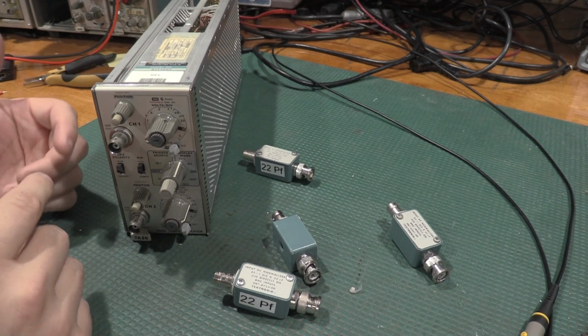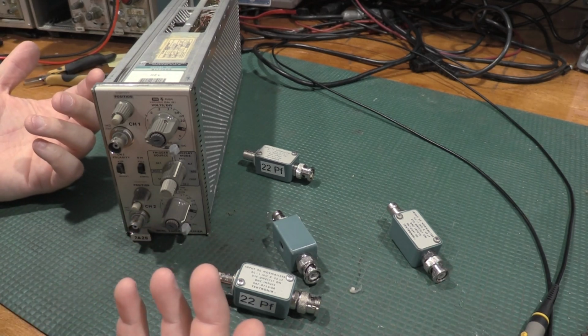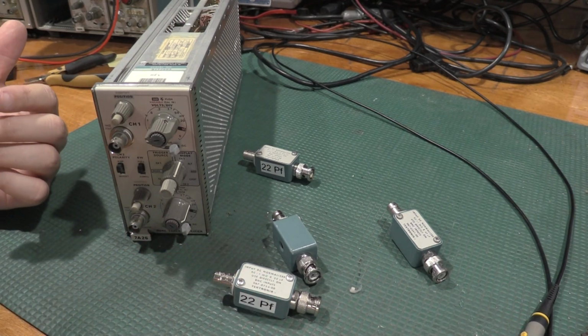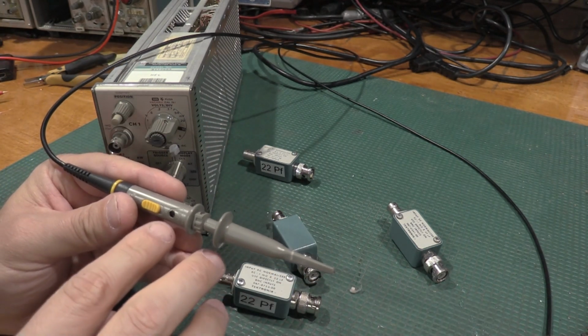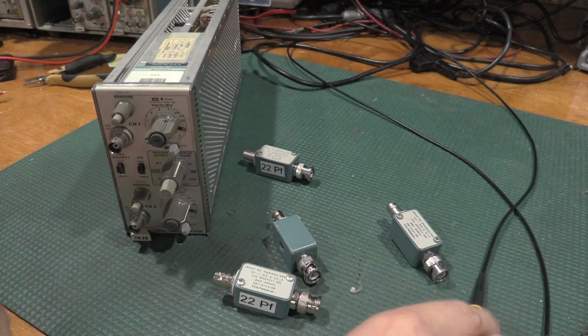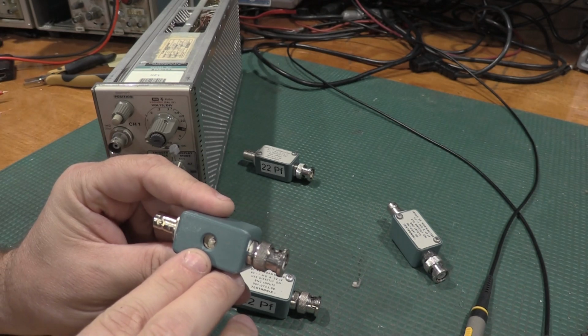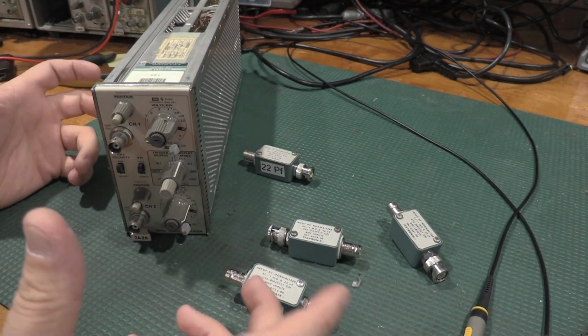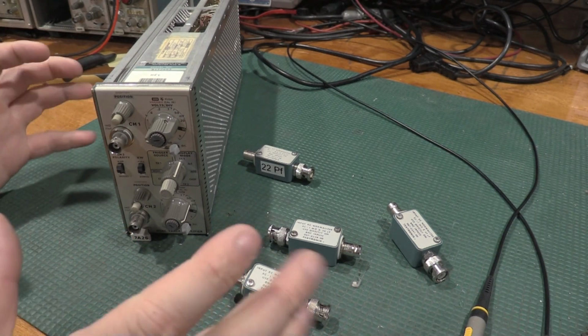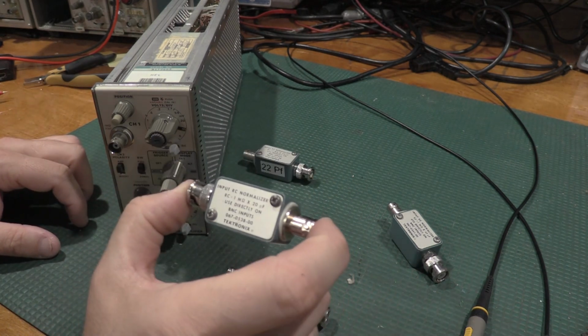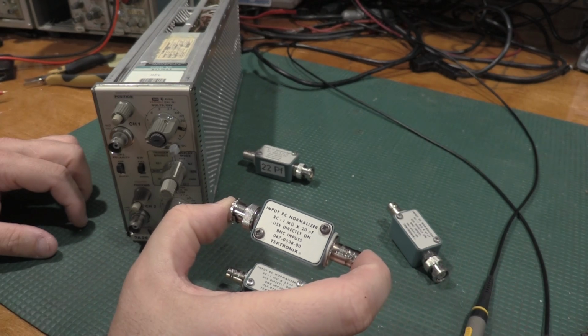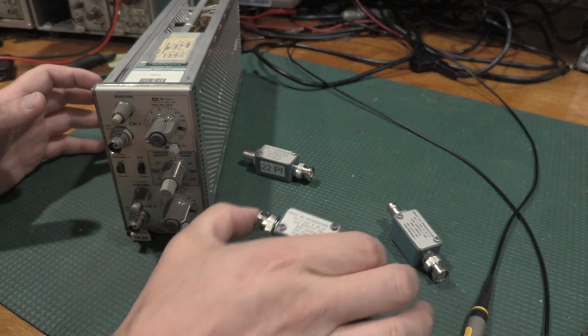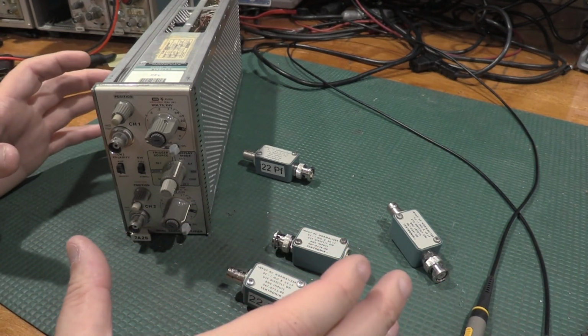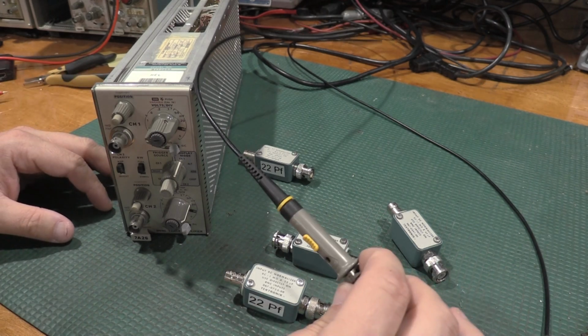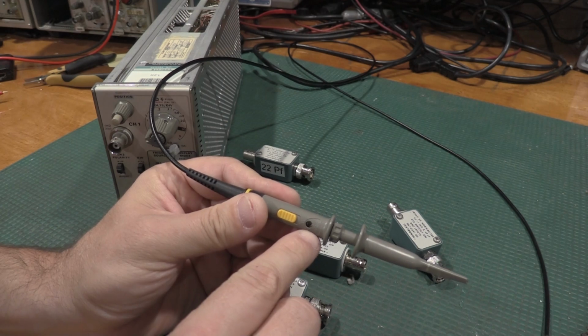This is so important because of probes. The probe has to faithfully pass the signal at the probe tip. Everyone's familiar with the compensation capacitor at the probe, and even these have a compensation capacitor in them. So, essentially, dummy probe. There's two ways to really use them. One way Tek does not recommend, which is set this to 20 picofarad and then align all the plugins to that. And if you do that in a really tight tolerance and tight standard, you can prevent having to tweak this capacitor every time you hook up a new probe to a scope.